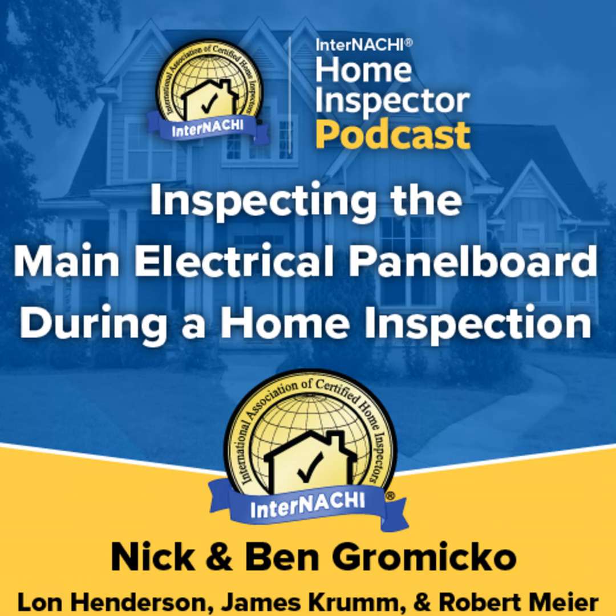Panel board and cabinet. A cabinet is an enclosure or box. The panel board contains bus bars, terminals, overcurrent protection devices, and mounting hardware designed to be enclosed in a cabinet. In residential wiring, the panel board is usually not distinguished as a separate piece of equipment from its cabinet because it is normally installed inside the cabinet enclosure at the factory. Most panel boards used in 1- and 2-family dwellings come from the manufacturer already installed in a cabinet. In this article, we use the word panel board to refer to both the panel board and its cabinet.